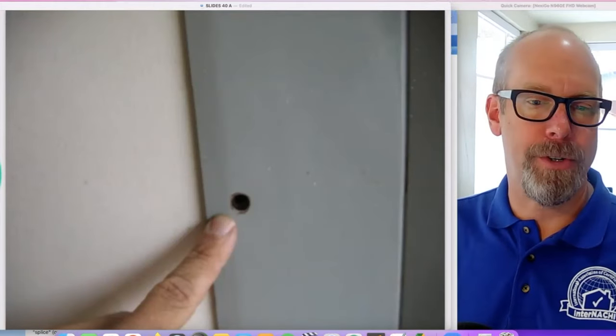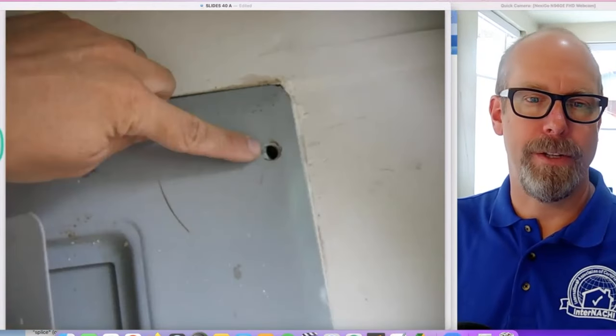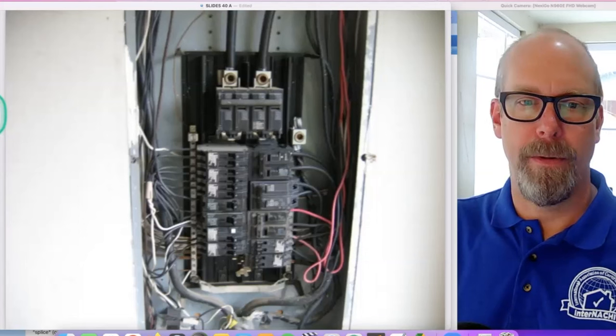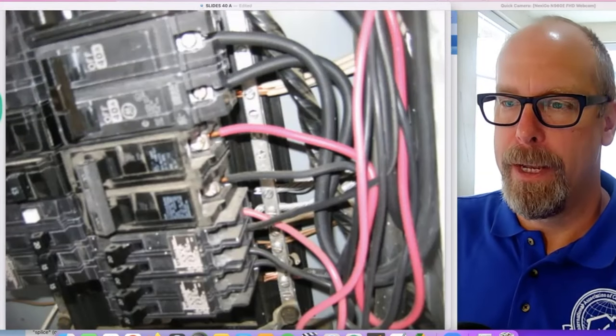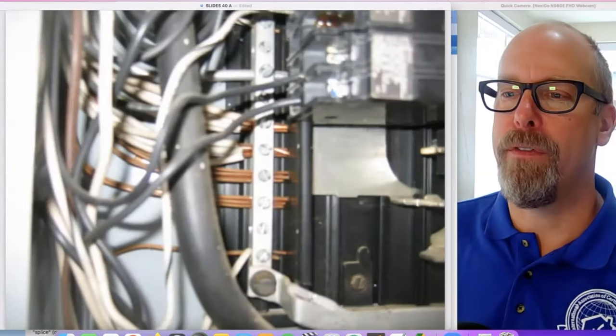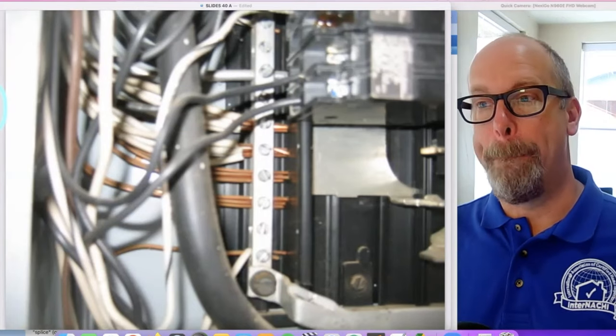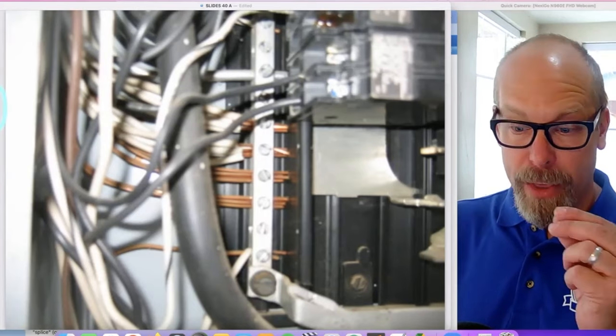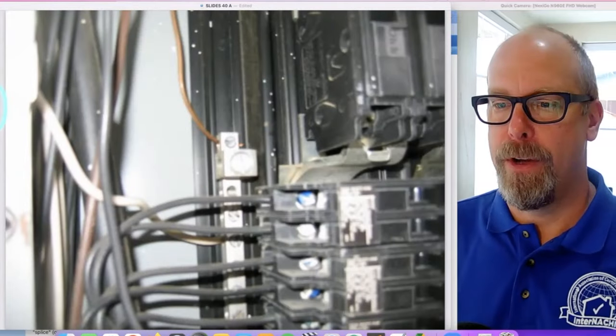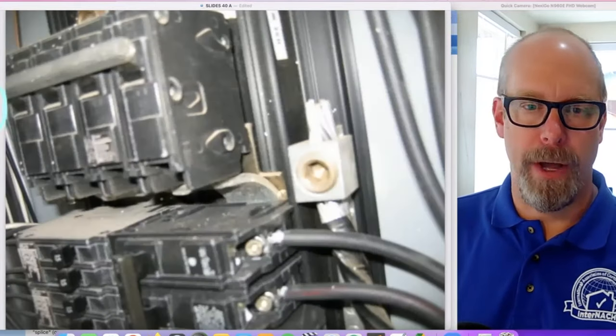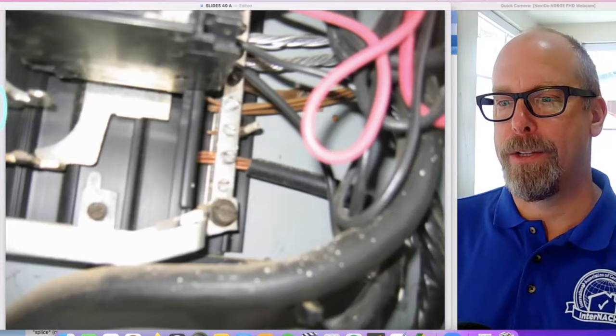I'm missing screws, panel screws. There's only two holding up this panel — two are missing. I'm looking at the wiring, looking for overfusing. I don't want a big fat 20 amp breaker on a very thin gauge wire — that's overfusing. Bonding, wires, grounding.